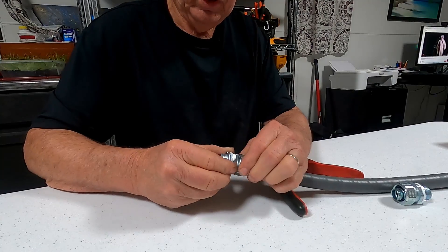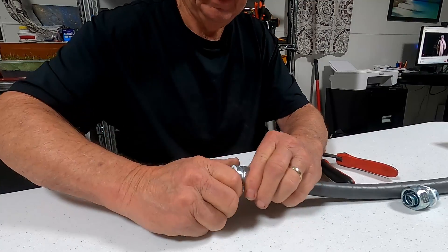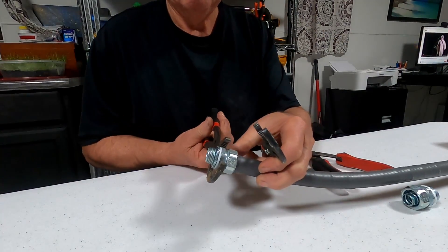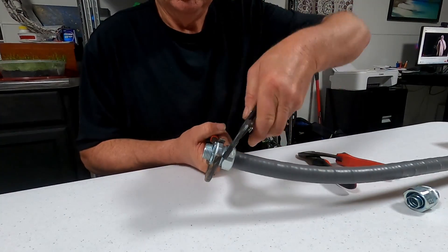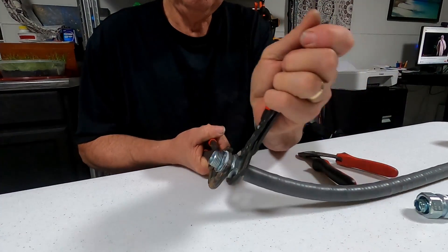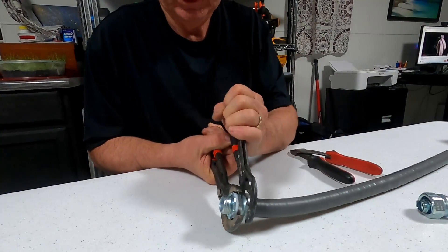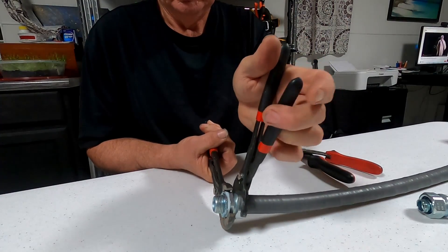So you screw it down until it's tight, then you take this piece, put it here, and when you tighten this down with pliers it crimps that inside piece onto the liquid-tight conduit. I'm going to grab it and tighten it with this, then take it back loose so you can see how it grips. This will not come off — plus it is a watertight seal.